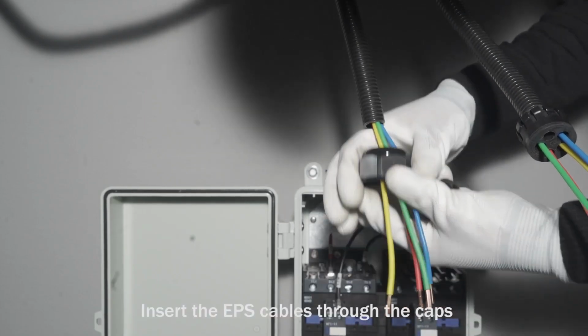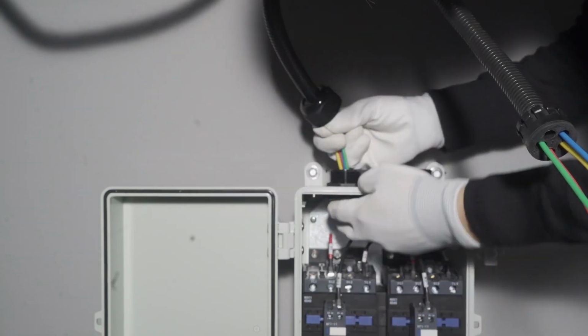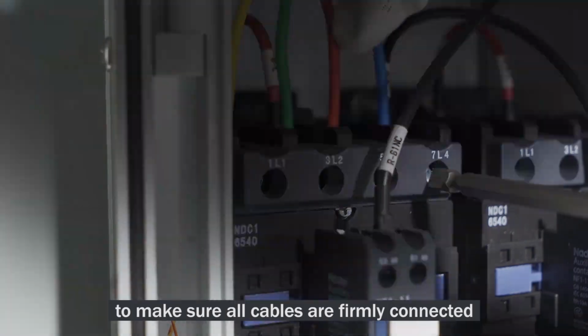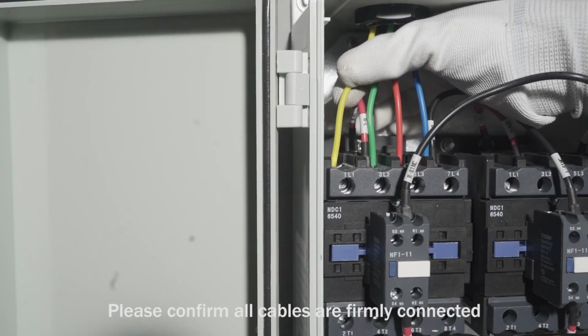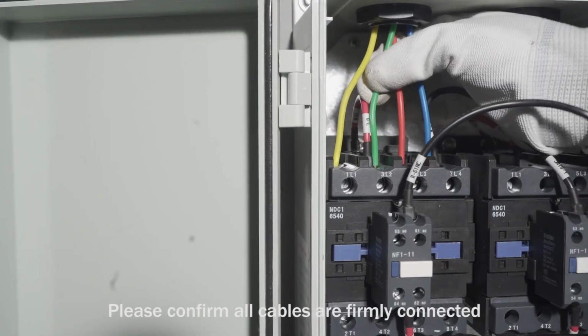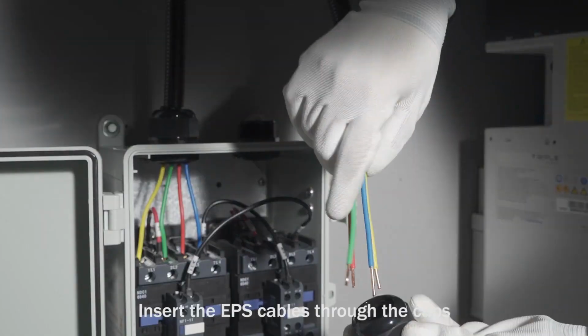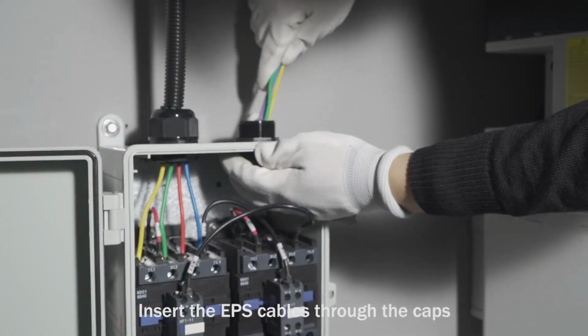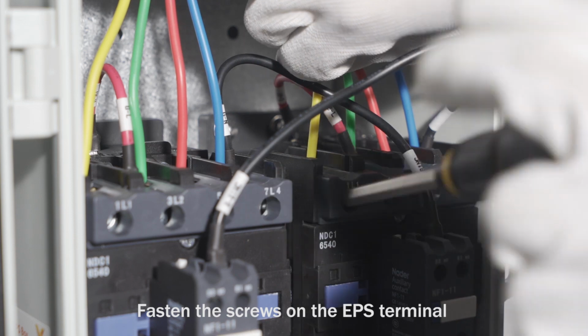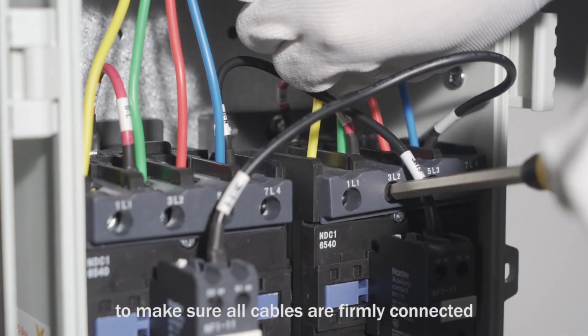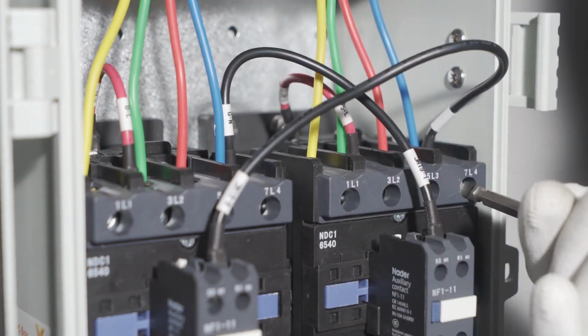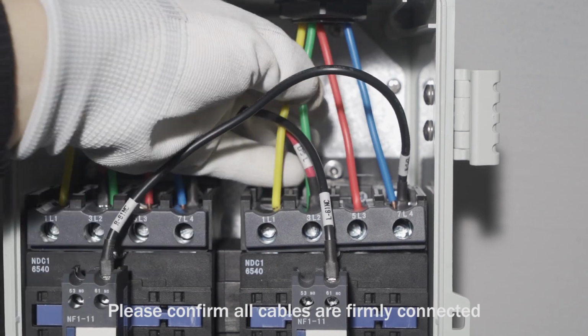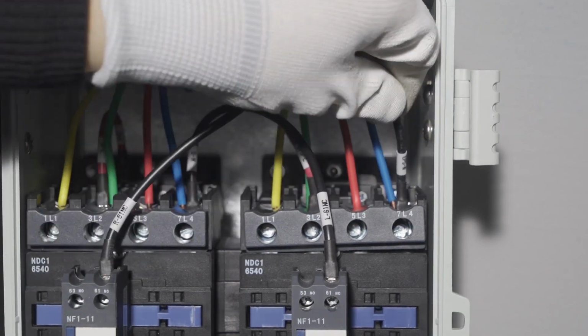Insert the EPS cables through the caps. Fasten the screws on the grid terminal to make sure all cables are firmly connected. Please confirm all cables are firmly connected. Tighten the grid nut. Insert the EPS cables through the caps. Fasten the screws on the EPS terminal to make sure all cables are firmly connected. Please confirm all cables are firmly connected.